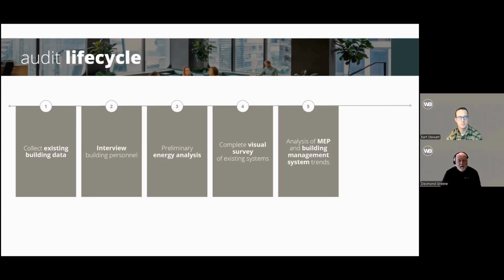For example, a typical EEM may be: we see a constant volume system serving a space in your facility—constant volume meaning a fan running at the same speed all the time. We may look at changing that to a variable air volume system, which varies the amount of air going into a space by modifying the fan speed, resulting in significant energy reductions. Our calculations encompass the cost of replacing the constant volume system with a variable air volume system, the associated payback, and any incentives or rebates tied to the reduction in energy.